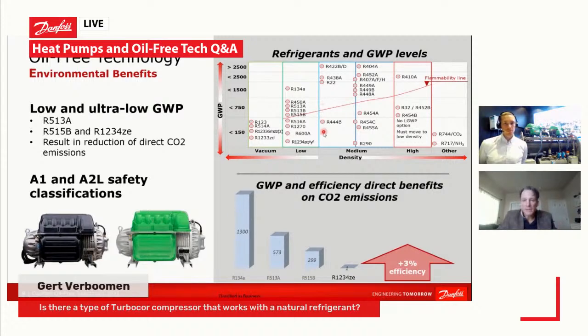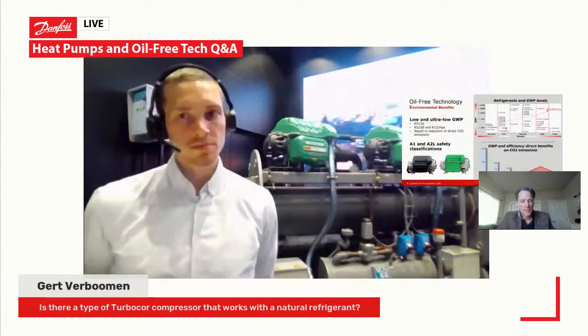Tying this back to the question, the primary refrigerant that fits into that low pressure category is 600A, which is isobutane, if I remember correctly. If we wanted to do an isobutane refrigerant-based Turbocor compressor design, because we have integrated power electronics in it, it would require significant modification to enable that, because otherwise it can be very hazardous having power electronics in the refrigerant flow path with isobutane. So, longer answer to your question, but today, no, we don't have any natural refrigerant solutions.